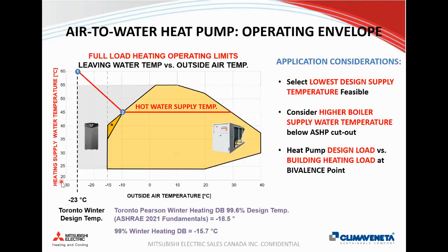So we'll go into the operating envelope here. So this example is based off Toronto, where we have a typical winter design temperature of about minus 23 degrees Celsius. So this operating envelope in yellow is showing us the maximum supply water temperature that the machine can supply for any given outside air temperature. So on the y-axis here, we have our heating supply temperature, and on our x-axis, we have our outside air temperature. And this is typical of what you'll find in the market from Mitsubishi or from other manufacturers making this type of equipment.